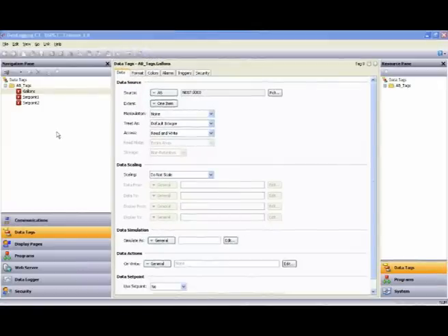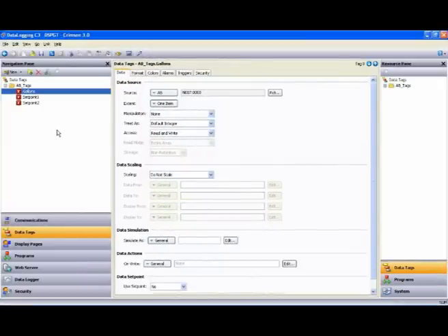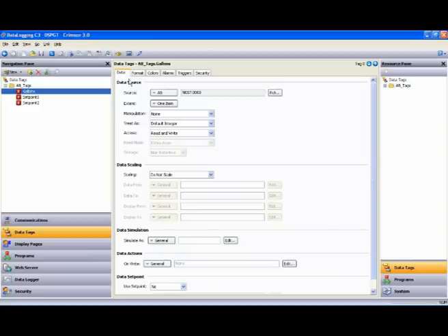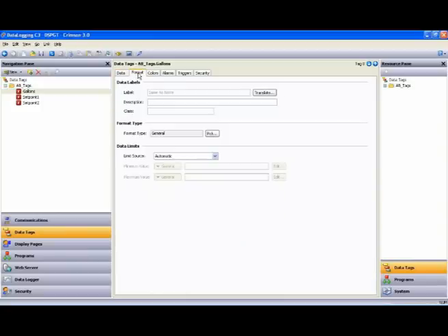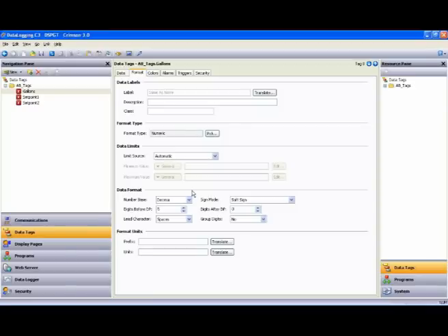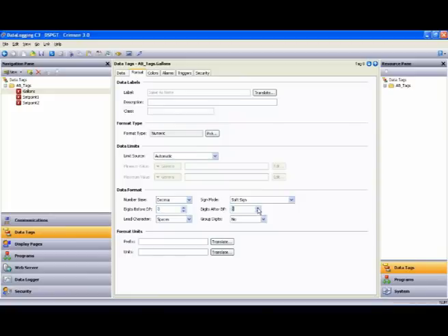Let's take a quick look at the mass editing of tags. If I wanted to change the formatting on my Gallons tag, I highlight that tag and then slide over to the Format tab across the top. And what I want to do is change the Format Type from General to Numeric. This enables a Data Format box that lets me configure the numeric field of that tag. So let's make the number of digits before the decimal point 3 and the number of digits after the decimal point 2.